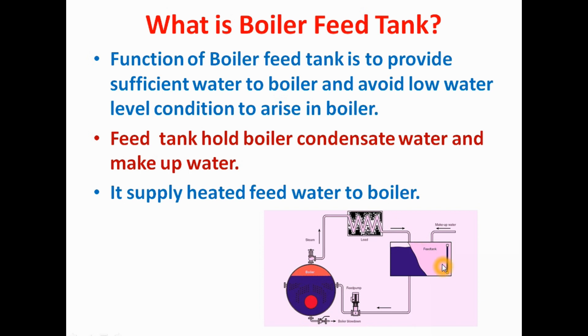This hot water is stored in a tank, which is known as the boiler feed tank, also known as the service tank. In this tank there is a sight glass for seeing the level, and there is an arrangement for makeup water so that the level can be maintained. This tank provides water to the boiler.